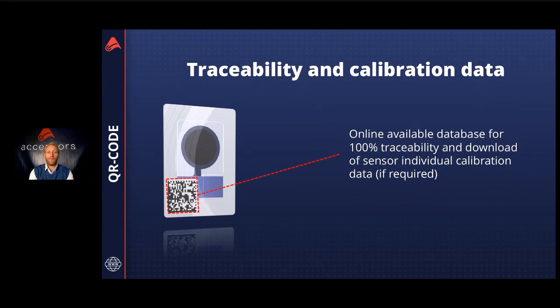And for this, and for the future, this means bringing our sensor element as a calibration-free element to our customers. We put a small QR code on every sensor element, and there will be an online-based database where you could read out all the relevant traceability ID data from this sensor, and in the future also the calibration data.